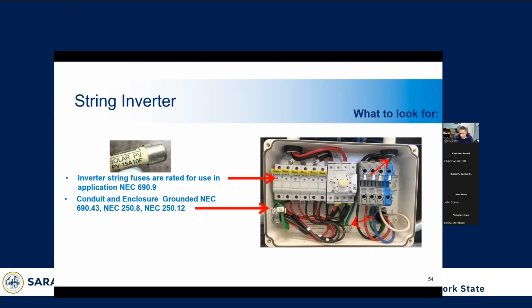And you also want to check for conductor sizing and markings, as well as fusing requirements. Fuses for solar PV systems have to be rated for solar, and you can't just use any DC fuse. And so fuses have to be rated for 600 volts DC in residential applications and 1,000 volts DC in commercial.